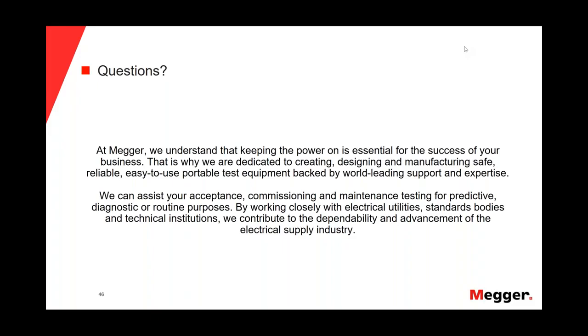Thank you, Sergio. Henning, would you agree that we should approach factory test results after installation under ideal conditions so that we can use factory test values as references? This brings back an old question. I think the common opinion on this is you cannot reproduce factory test results, which are taken in a completely noise-free Faraday cage environment, and expect to see the same in the field, okay? Because in the field you don't have this shielding. You have wherever the situation is, you have to deal with it. You have to deal with the background noise also.